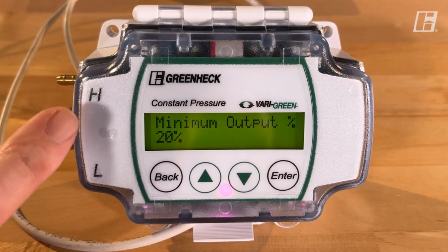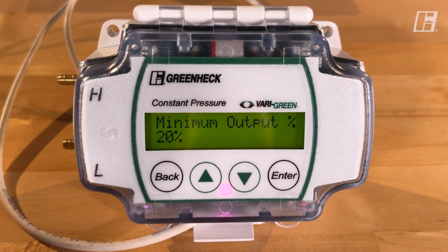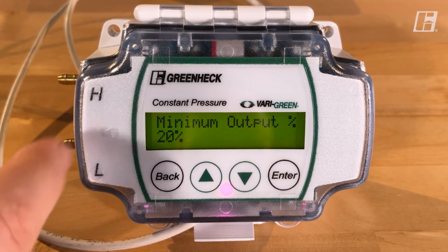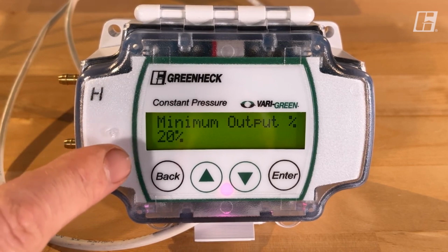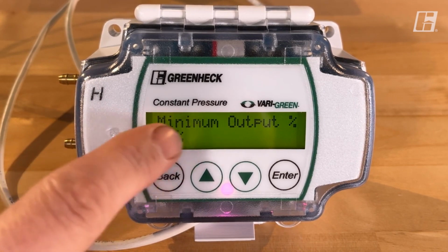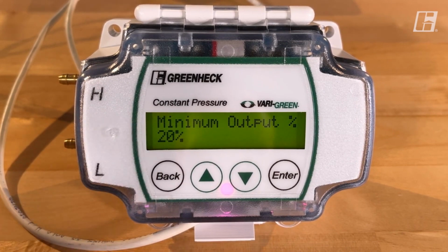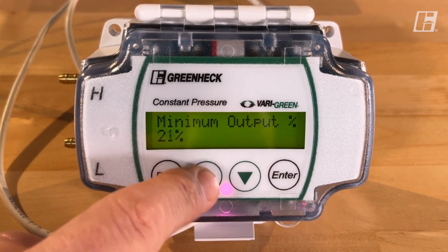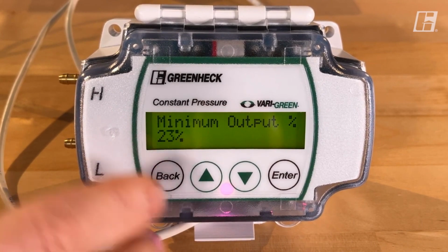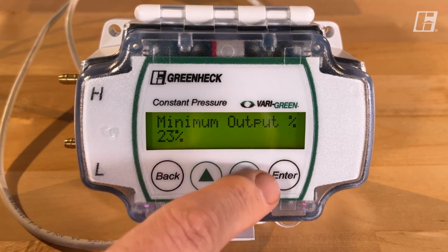So we have a parameter here that allows us to define how slow the fan can go. A typical Vari-Green motor can go as slow as 20% or as fast as 100%. So this is saying we can go all the way down to the bottom. But if you wanted to maintain at least a certain amount of airflow, you could easily set this at 22 or 23 and not let it slow all the way down.